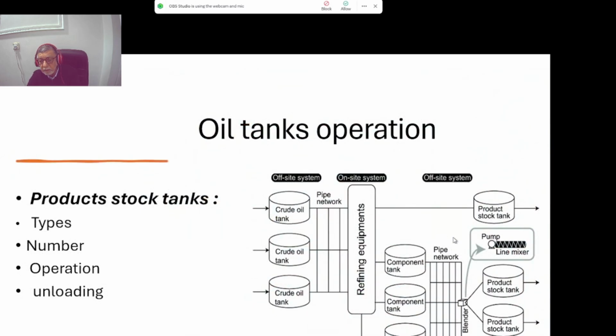For the final products we also use these tanks. Spherical tanks are used for LPG, which does not appear here. For the other types, we have reformate and isomerate first. Isomerate needs floating roof tanks. Reformate also uses floating roof tanks. Kerosene, or jet fuel after it is made, can use either floating or fixed roof tanks, and diesel uses fixed roof tanks. Long residue or heavy oil needs fixed roof tanks equipped with an internal heater.